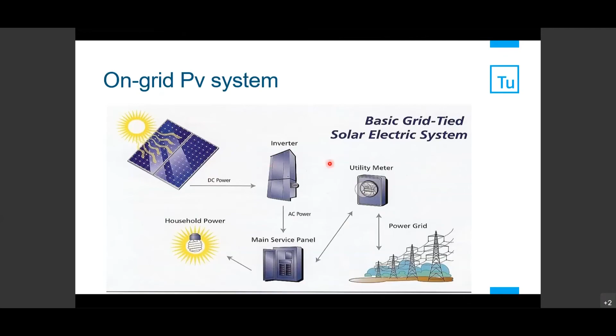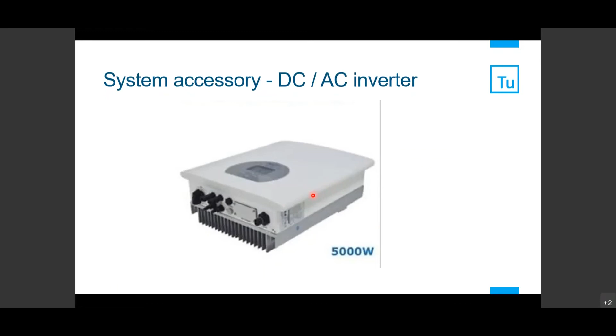So here is an example of one of the possible DC-AC inverters. This device converts DC power into AC power, because the current the solar system generates is direct current, as we said, and the general loads are AC loads. So the inverter is indispensable, and a grid inverter is used in on-grid solar power generation systems. It can feed the electricity generated by the system into the national grid, and you must have this in this approach. Also, it has to ensure anti-islanding.